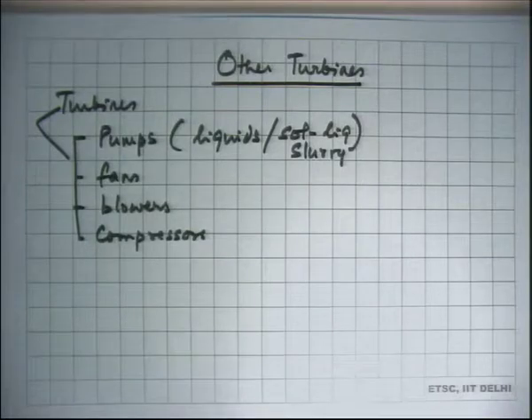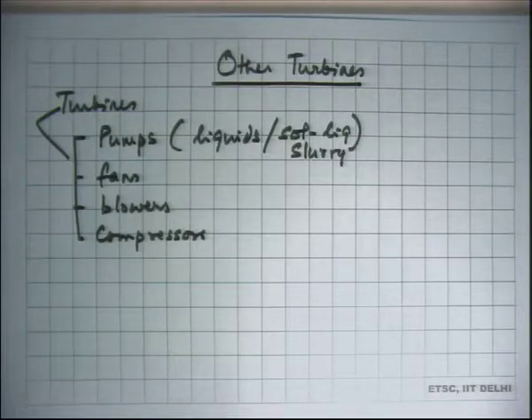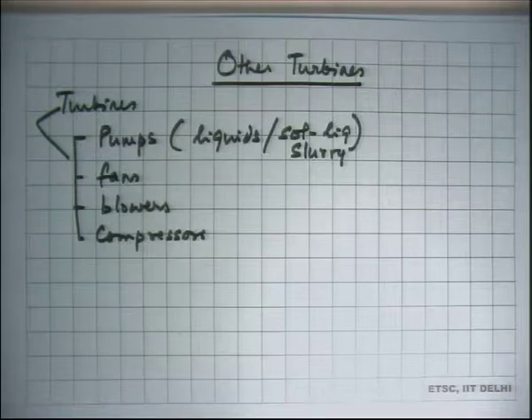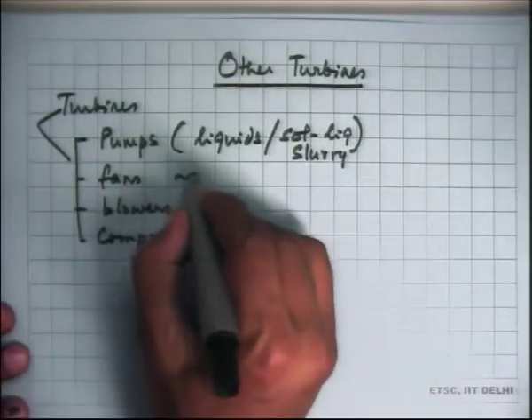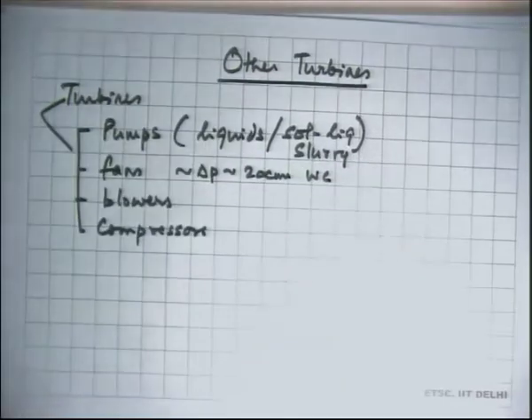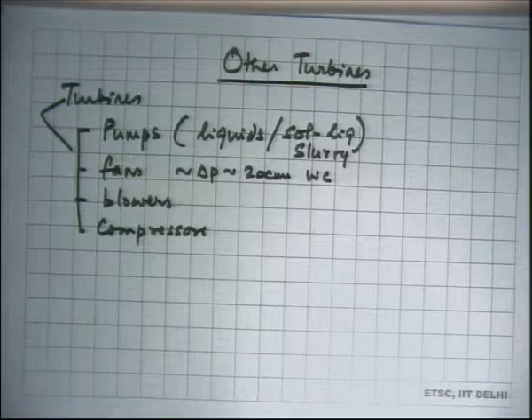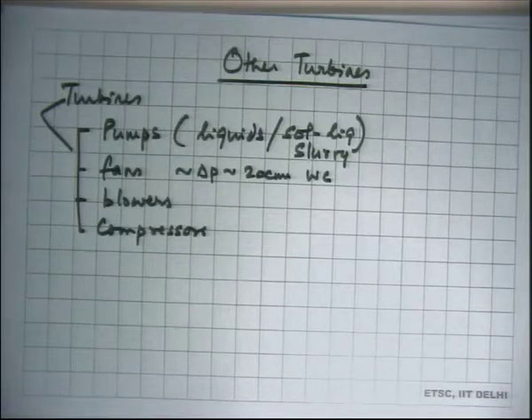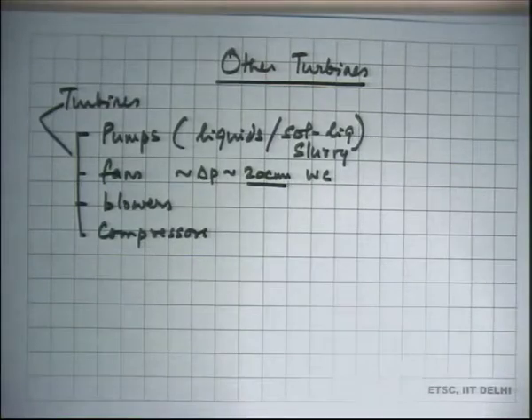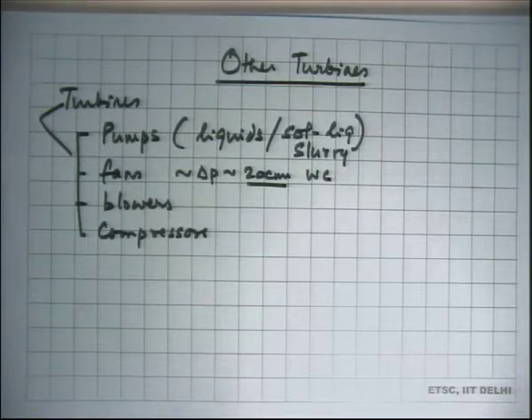Fans are devices which produce a small pressure rise in air streams — pressure rise delta P up to about 20 centimeters of water column. If you measure the pressure difference between the inlet and outlet of the fan using a manometer with water as the working fluid, you get a maximum of about 20 centimeters of water column. These are low pressure rise machines, usually used for very large air flow rates but small pressure rise.